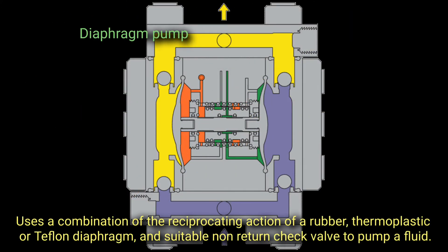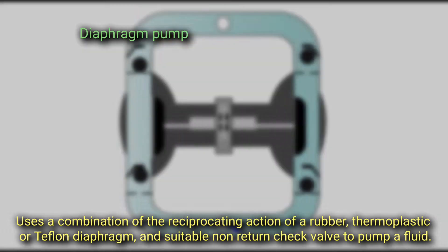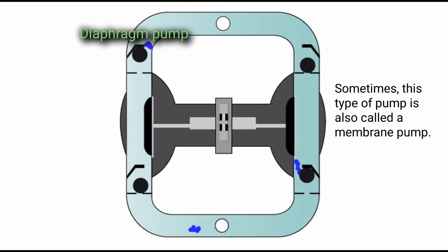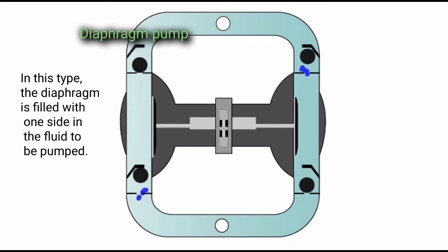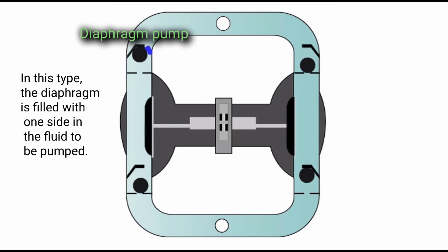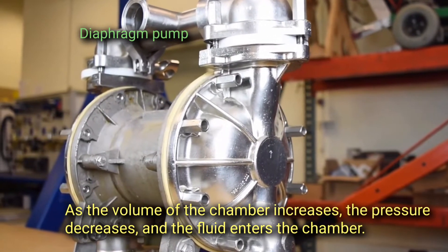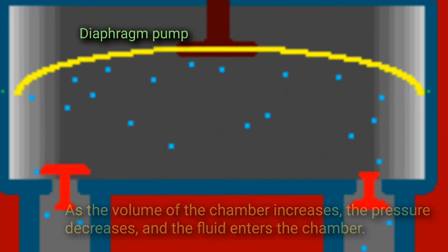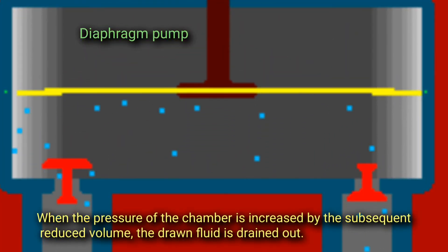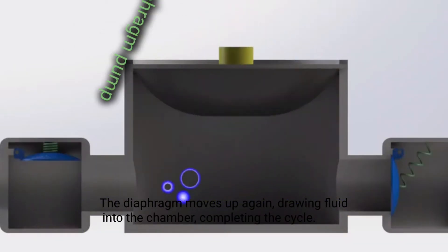A diaphragm pump uses a combination of the reciprocating action of a rubber, thermoplastic, or Teflon diaphragm and suitable non-return check valves to pump a fluid. It is sometimes called a membrane pump. In this type, the diaphragm is filled with fluid on one side. As the volume of the chamber increases, the pressure decreases and fluid enters the chamber. When pressure is increased by the subsequent reduced volume, the drawn fluid is drained out, and the diaphragm moves up again — completing the cycle.